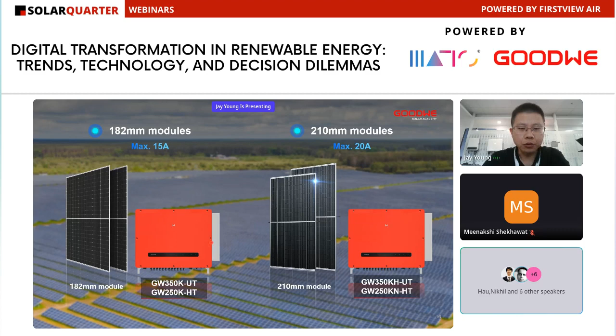So in the market, we noticed that the majority of modules are of one type that exports 15 ampere, and another type that exports 20 ampere. Both the 250 and 350 are compatible with these PV modules. And for the PID solution, especially when the utility station is near the seaside or near a lake, or in a very high humidity environment, it is easy to get the PID effect, which will reduce the life of the PV modules and reduce the power generation.